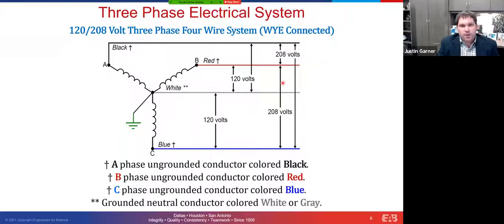One thing to note here, if you have some smaller HVAC equipment that may border on the residential or light commercial side, and it may be dual rated for a 230 or 240 volt or 208 system, the way that would be connected here would be between two of the ungrounded conductors within the system. So if you see a motor, and we're going to talk more about motor designations as we go through the presentation, but if you see a motor that's rated at 208 to 230 volts, and you have a system like this, well, you can't get 230 volts out of this system, but you can connect that motor to two legs of a 208 system, and it will operate. Understand it's going to operate at a different amperage, and we'll talk about that a little bit later on, and you may have to wire the motor differently for it, but that's going to be manufacturer dependent. So just be aware of that.